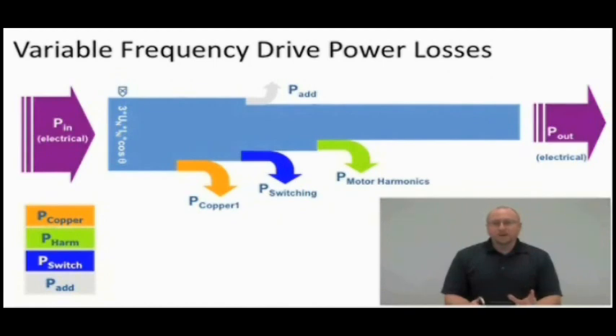So a VFD has the same losses as almost any electrical component. There's going to be copper losses. Everything that's electrical has copper losses. There's current going through wires, or in this case, through the traces on the circuit board, and they create heat, and that's a loss of energy. There's switching losses. That's a little bit different. With an inverter, we have output transistors. They turn off and they turn on. That's going to be a loss.